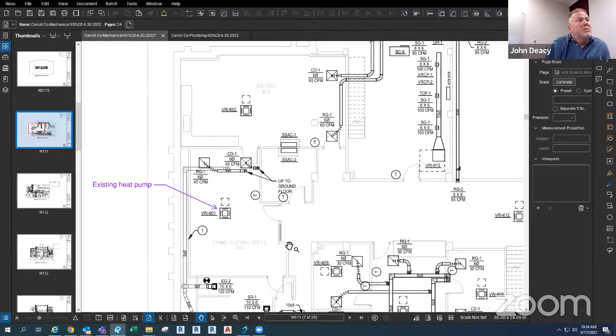Just the same as what was on it. So your room needs to be on the emergency generator, and it's not. If you put it on the VRF, it will not be. Would the HVAC in that room need to be on the emergency generator? Because if you put it on the VRF, it most likely will not be.